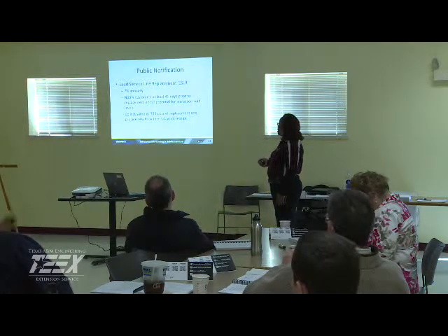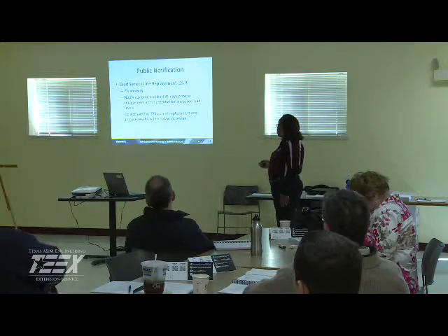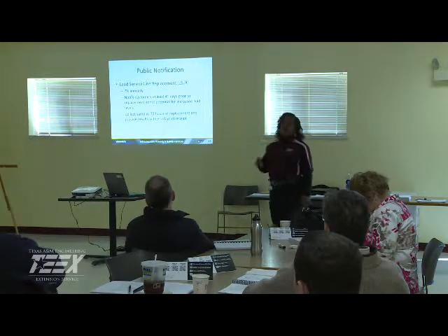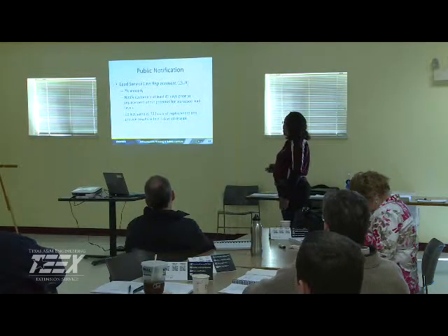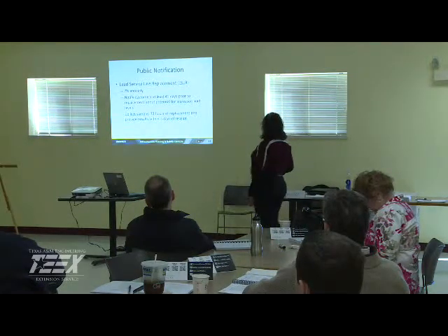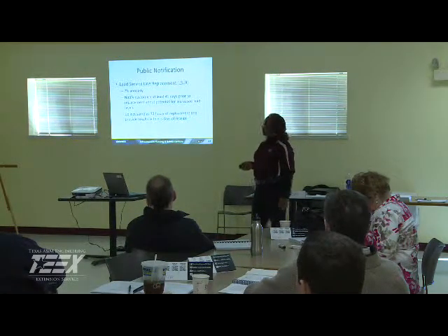We talked about the lead service line replacement, at least 7% annually. You must notify your customers at least 45 days prior to replacement, because there may be an increase in lead levels while you're undergoing that construction. Collect samples within 72 hours of the replacement and then provide results within 3 days of receipt.